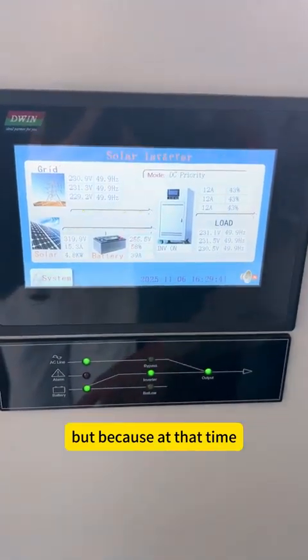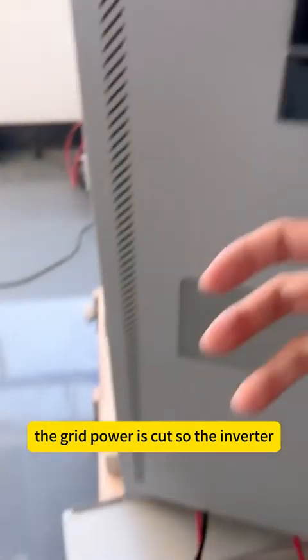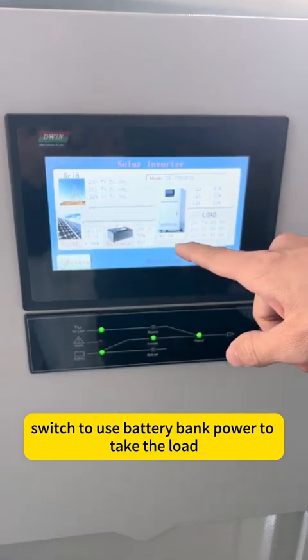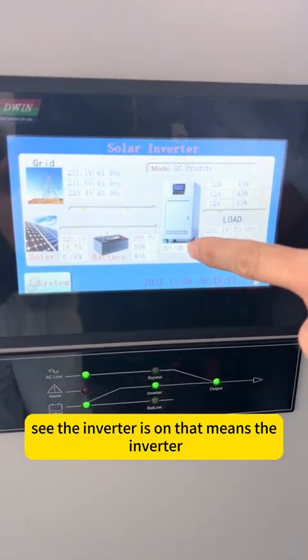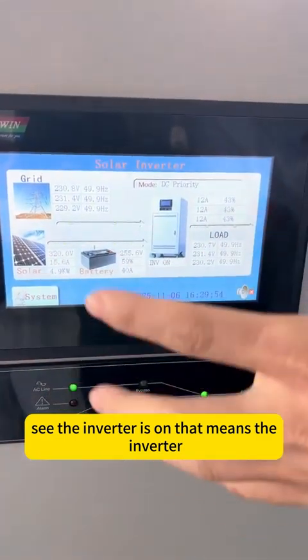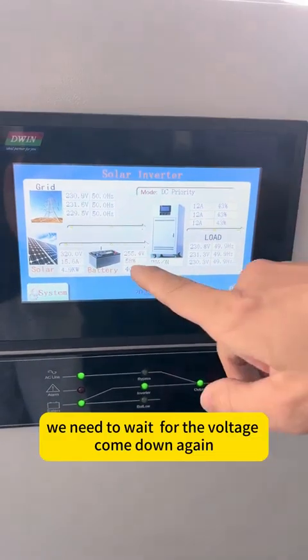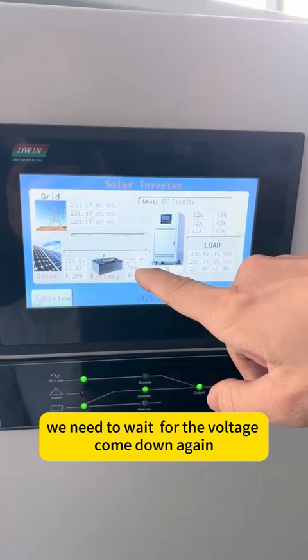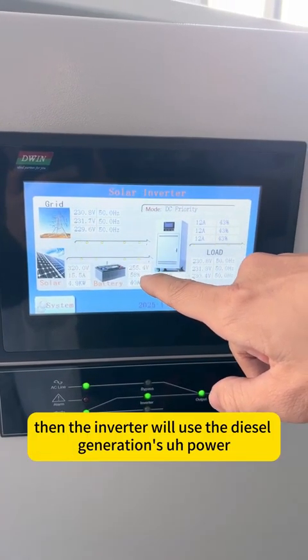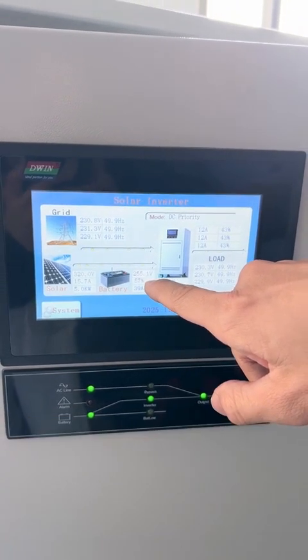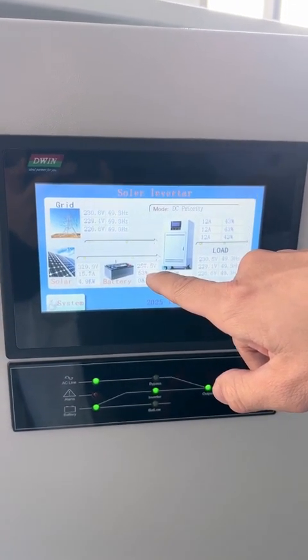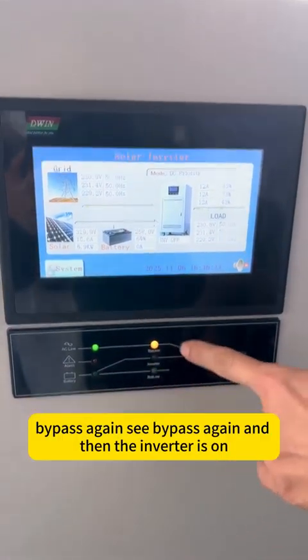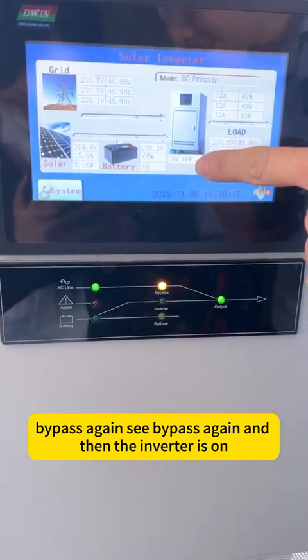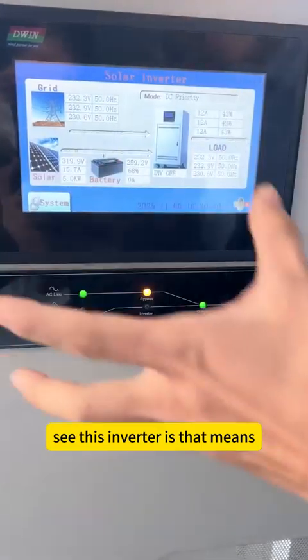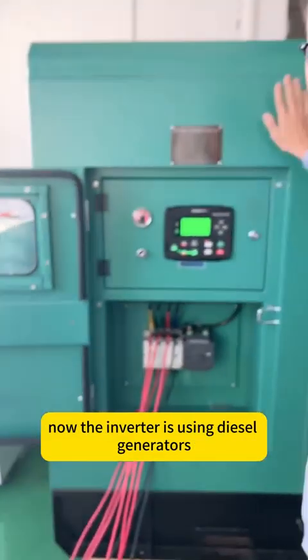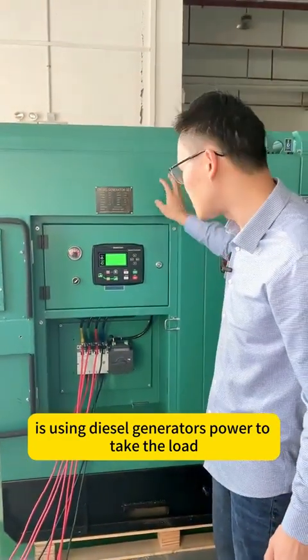But because at that time the grid power is cut, the inverter automatically switches to use battery bank power to take the load. That means, you see the inverter is on. The inverter right now is using the battery's power. We need to wait for the voltage to come down again. Then the inverter will use the diesel generator's power. Bypass again, and then the inverter is on. That means now the inverter is using the diesel generator's power to take the load.